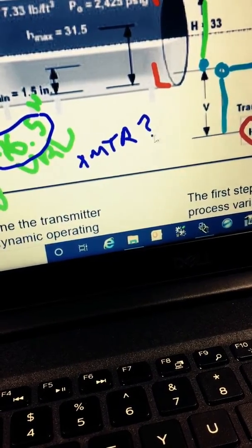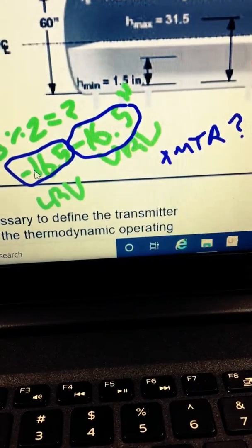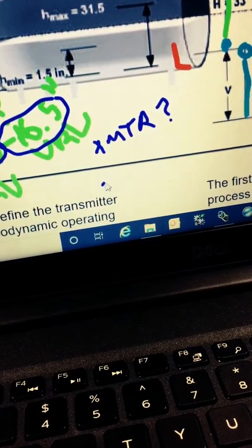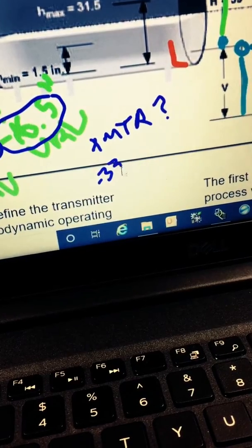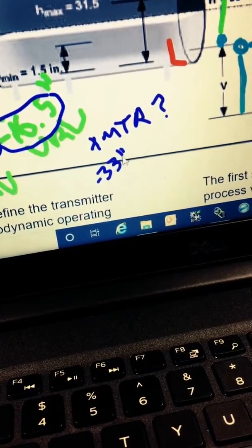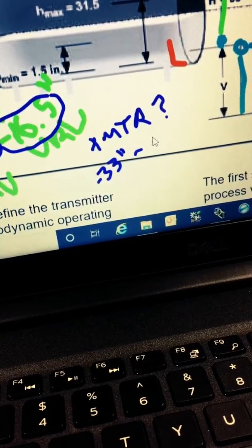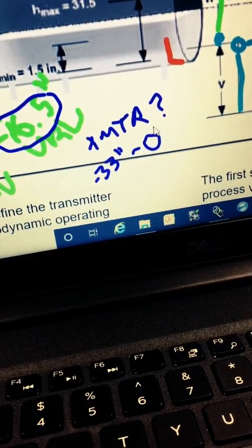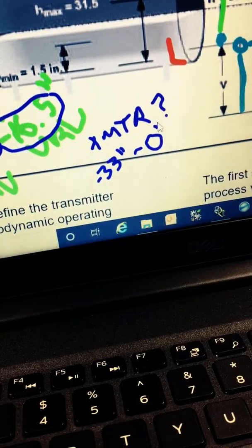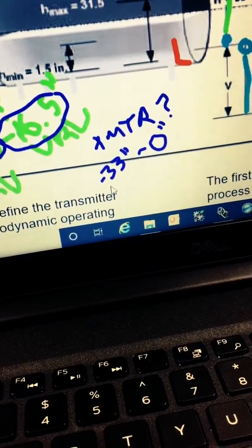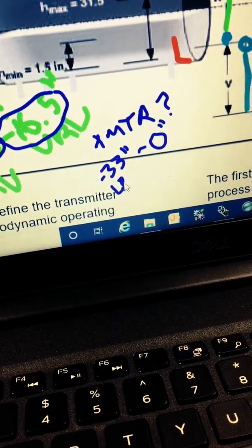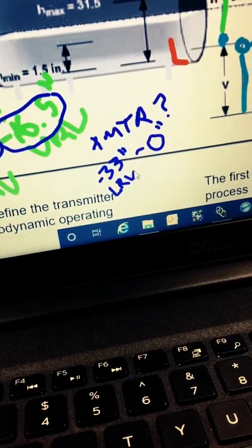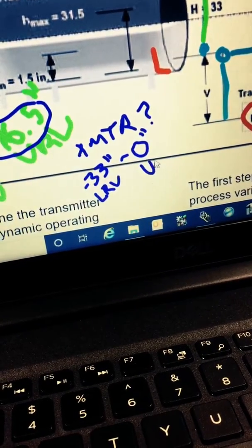So, what is our transmitter range going to be? If you listen to the other podcast, you probably guessed it. It's going to be 33 inches, because it's going to have a difference of 33 inches. So, what you're going to see here is because it's tapped low of the drum to the high side of the transmitter and high of the drum to the low side of the transmitter, you're going to have a minus 33 inch lower range value and you're going to have a zero inch upper range value.